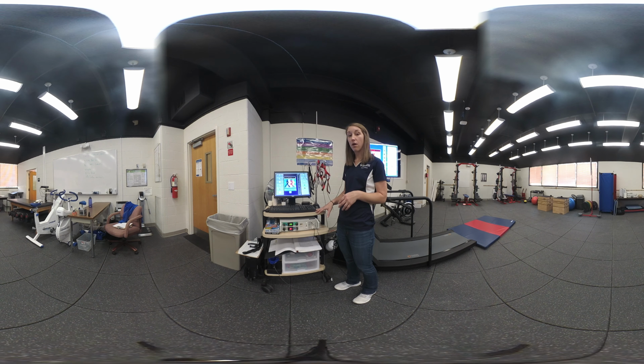So in a metabolic cart which takes a full sample, you have big bulky tubes that are collecting all the air that the subject's breathing in and breathing out to send into the metabolic cart unit. For our sample, we have these very narrow tubes which are a lot lighter to hold up, and they tend to be more comfortable for the subject because they don't require as much headgear. Our samples are a little bit less accurate because they're fractional samples as opposed to something that's pulling in all the air instead of a fraction of the air.